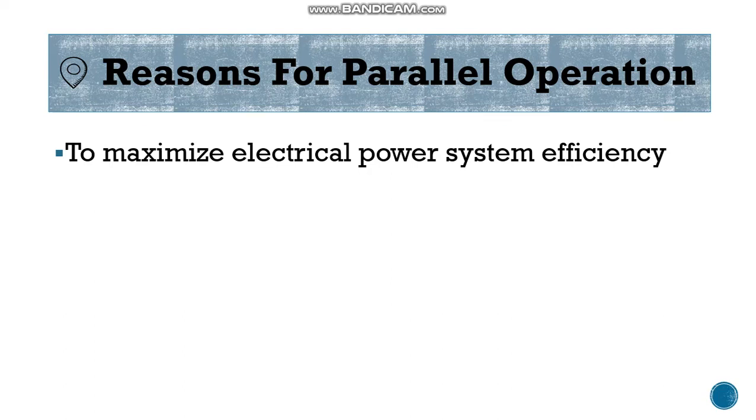Let's say 50 amperes rated transformers and yung load is 200 amperes. So para makuha yung maximum efficiency, kailangan maglagay ng apat na 50 amperes rated transformers in parallel at kapag yung load naman ay 50 amperes, remove the other transformers and connect the single transformer. Ito yung overall na pag-increase ng efficiency ng system. You are using the system for what it is designed.